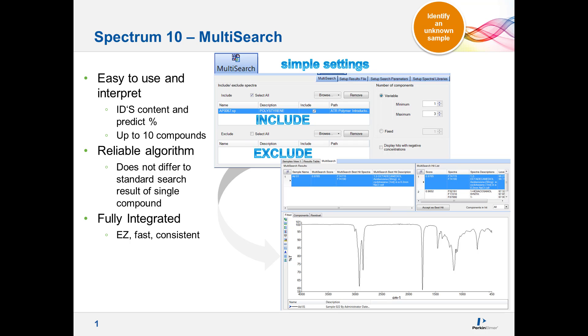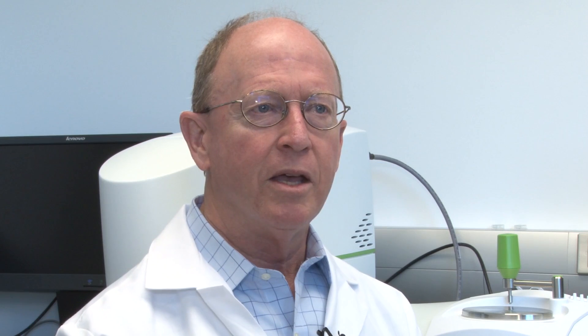PerkinElmer once again comes to the lab rescue with our new multi-search capability. Multi-search was specifically developed to identify these unknown mixtures. With multi-search, a user can search and identify up to 10 individual components in a mixture, just like traditional search routines. This works best with user-generated libraries and with any commercial libraries. But the main difference is that multi-search looks for similarities between unknown compounds and combinations of reference compounds in the search library.